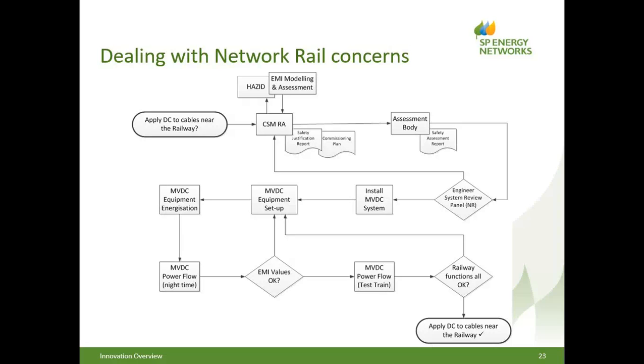If they're happy with all what we've assessed and all the conclusions and the outputs and the mitigation methods, whatever we come with, we have to do. We haven't had the Hazard ID workshop yet. Then that will give us the thumbs up to go ahead and install the MVDC equipment. If we do need to do anything, particularly filtration of harmonics or something like that, then obviously doing this pre-installing the equipment gives us an opportunity to factor in some additional filtration on the DC side should we need to do that. We then move into putting the equipment in, energization, set it up.